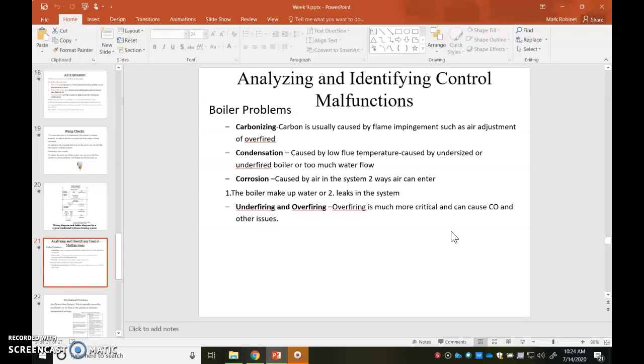So carboning is usually caused by flame impingement or such as air adjustment or overfired. Carboning is a very black, fine dust. It's not really a dust, it's a chemical, black carbon. You'll see it on candles, that kind of stuff, right? When it happens on a boiler, it is a mess. And you have to completely disassemble the boiler to try and get rid of this carboning. You'll want to get rid of all of it.